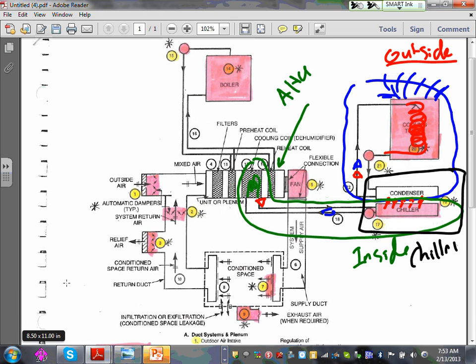Now what's your job and my job, guys, is the power. I'll show you how this equipment needs power. A lot of this highlighted equipment needs power, so we're supposed to power them. Any comments, any questions about the cooling tower interface with the chiller, interface with the air handling unit? Two separate closed-loop water systems. One water system goes between the condenser and the chiller, inside the chiller body, and the other one from the chiller directly into the air handling unit. They don't interface, these two water loops, guys.